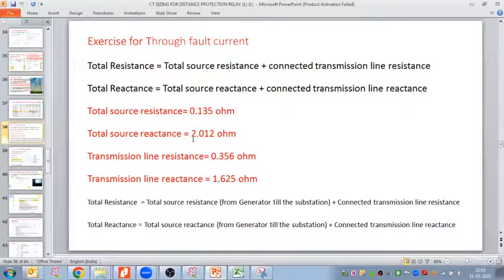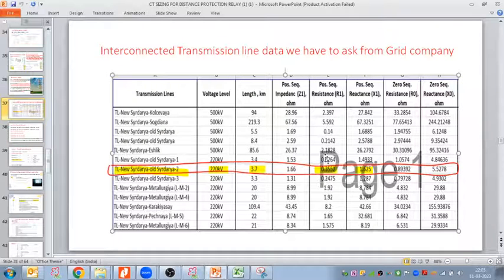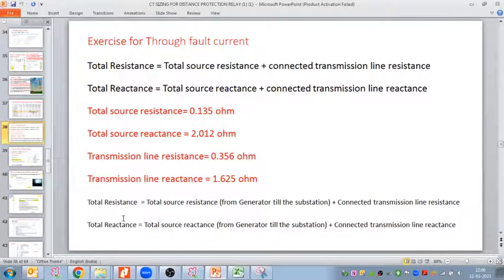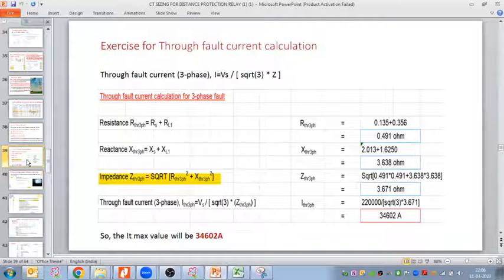Now the transmission line resistance and reactance we got are 0.356 ohm and 1.625 ohm, from the grid, from the client. So now we add both the resistance and reactance. Total resistance is the total source resistance plus the transmission line resistance. Similarly, the total reactance till the fault point is the total source plus the total transmission line reactance. Now you know why we did the calculations for the source resistance and reactance initially. This we already know, and this we know from the grid company.